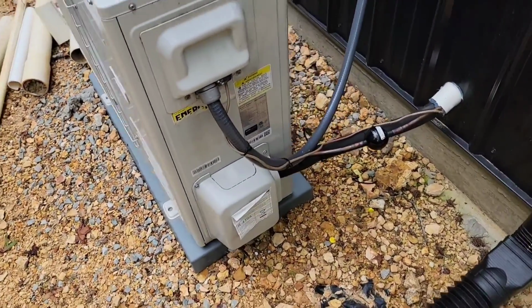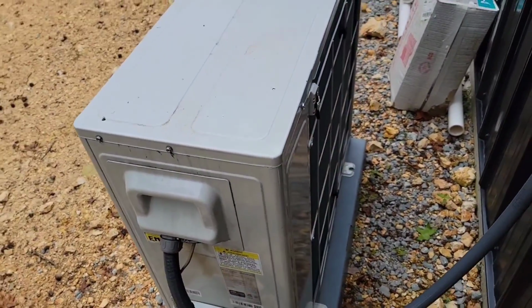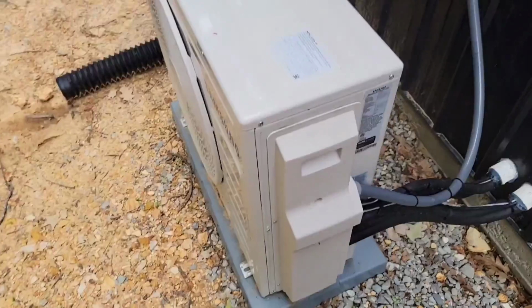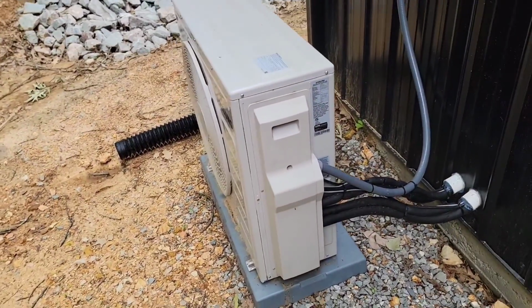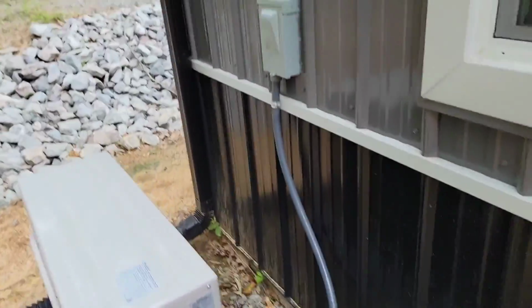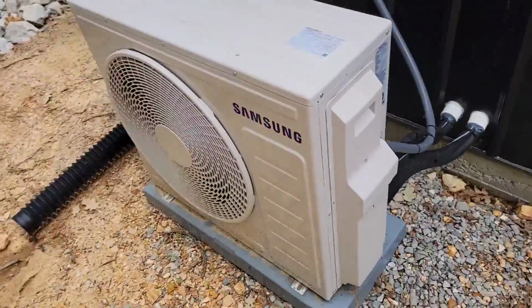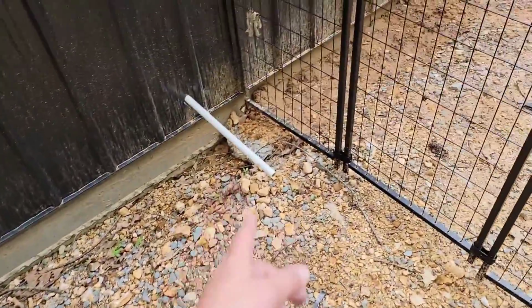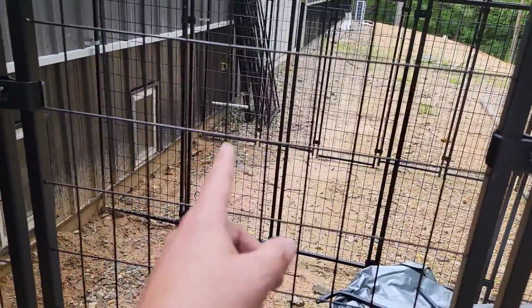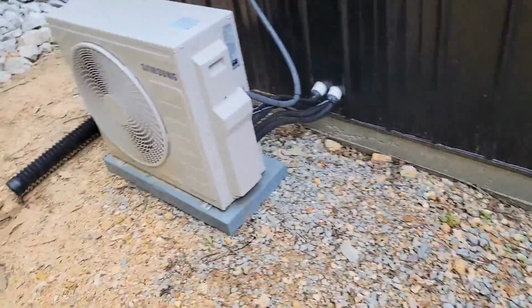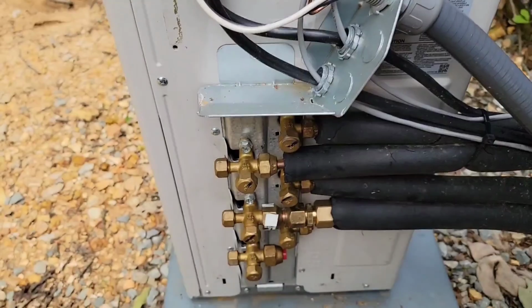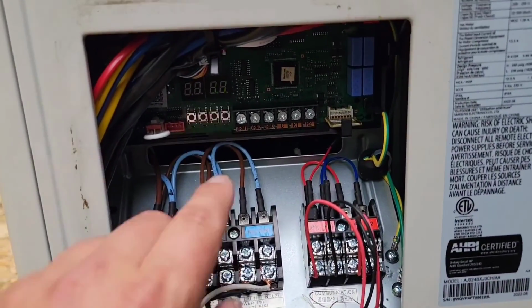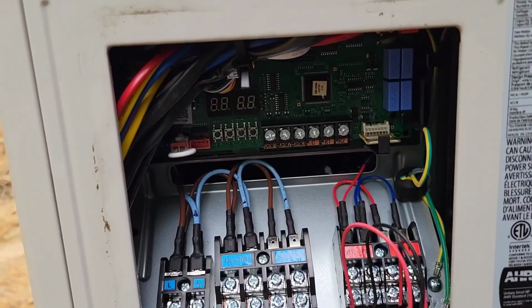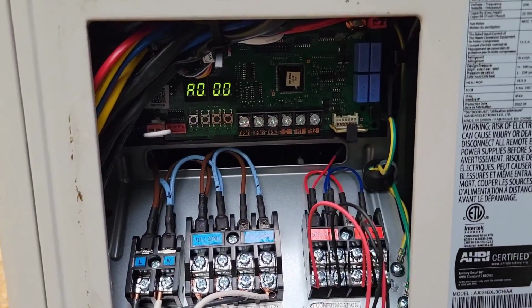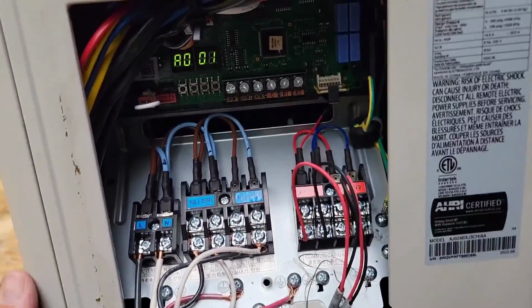Outside condenser looks great. This is the HMH7. Disconnect on the wall. Samsung 2 ton with 2 heads. Looks good on a nice pad. There's a disconnect. Got the drain for this one, and then you can see that drain over there for the other one. Looks good. Power's on to the Samsung free joint multi. Oh, it's already recognized the heads. 0 and 0, 1. Okay.